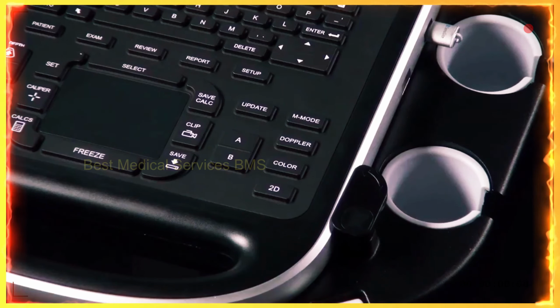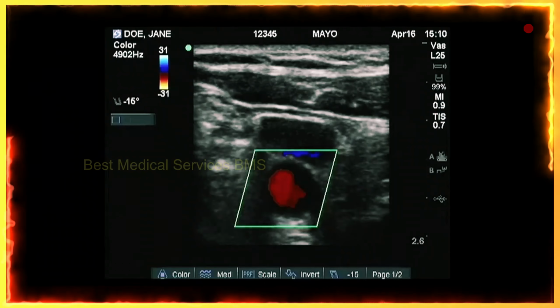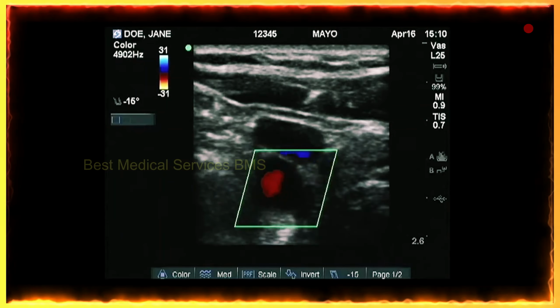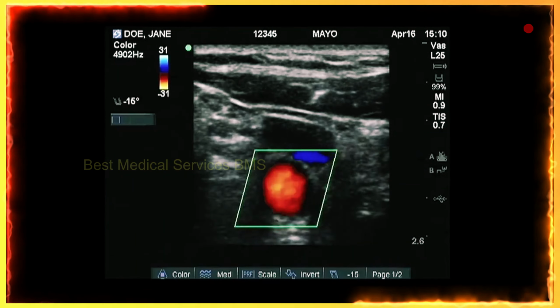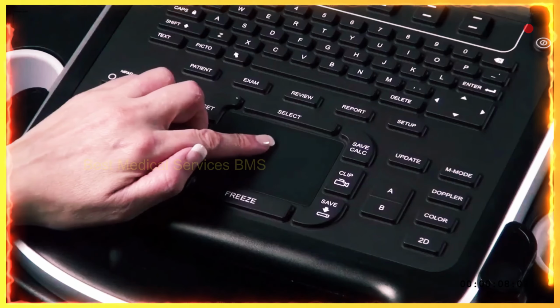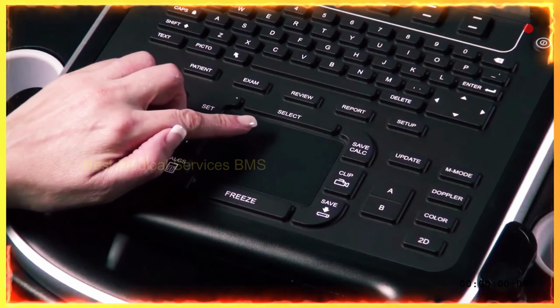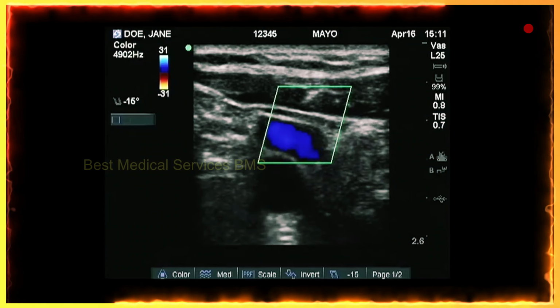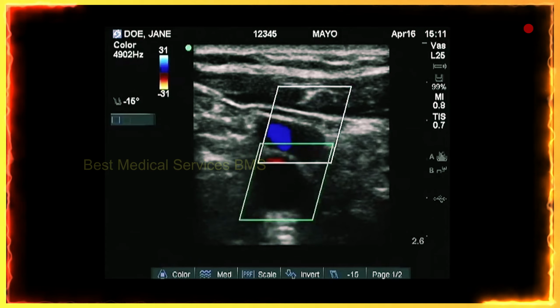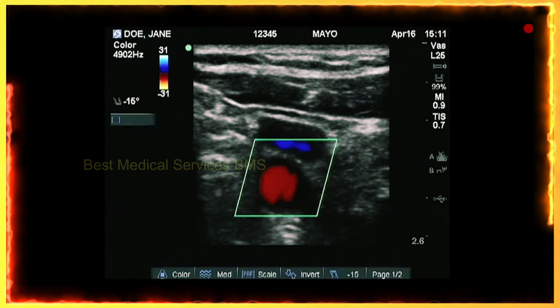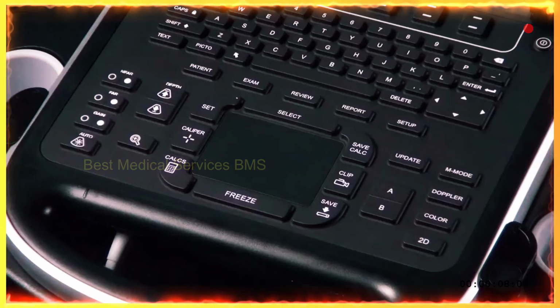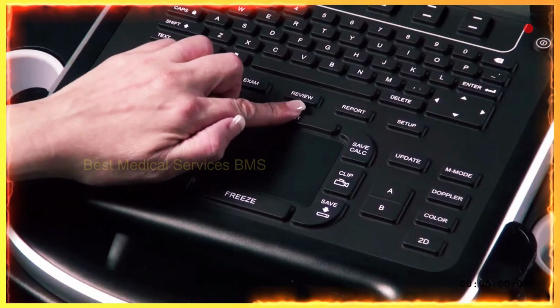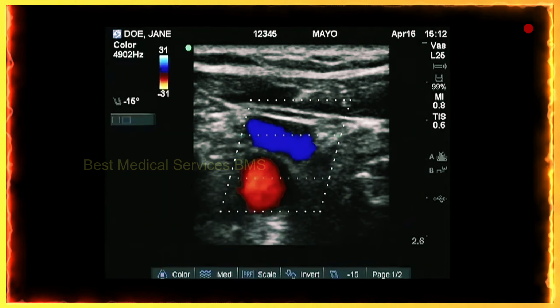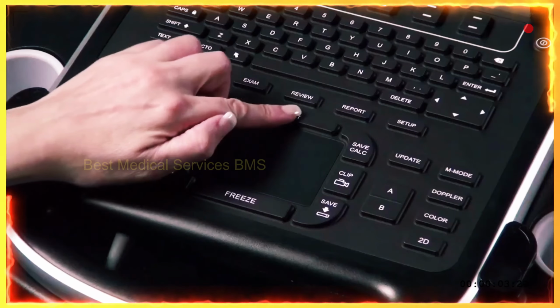Press the Color key to activate Color Doppler or Color Power Doppler. A region of interest, ROI box, will appear in the center of the screen. Use the touchpad or arrow keys on the control panel to change the position or size of the ROI box. Use the Select key to toggle between changing position or size of the ROI box.